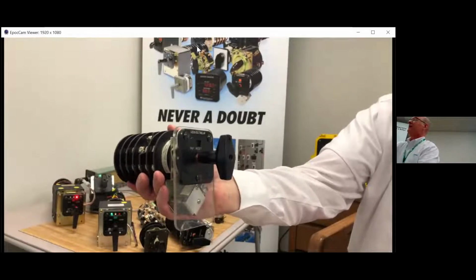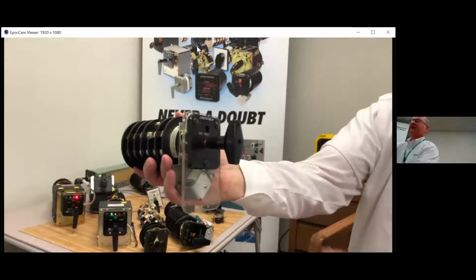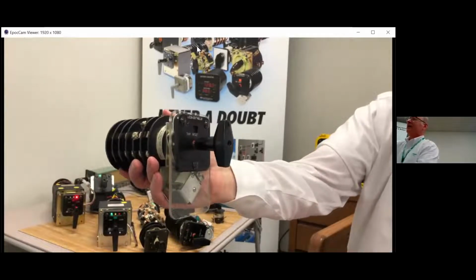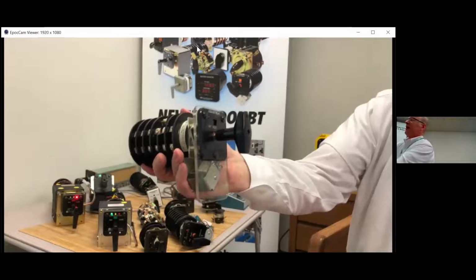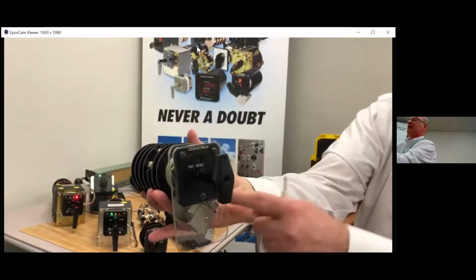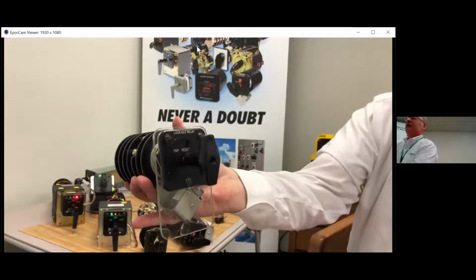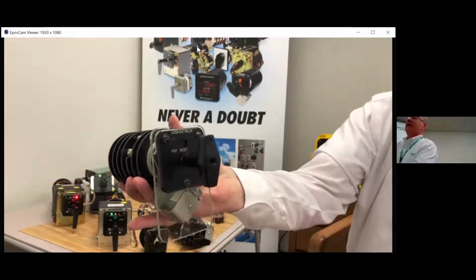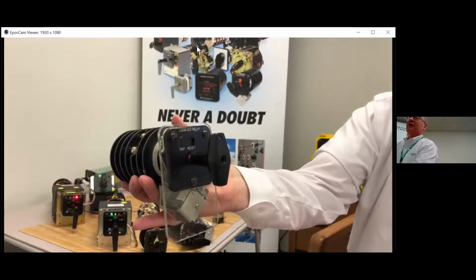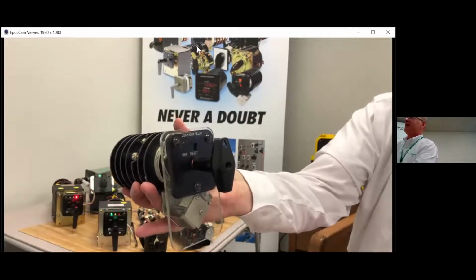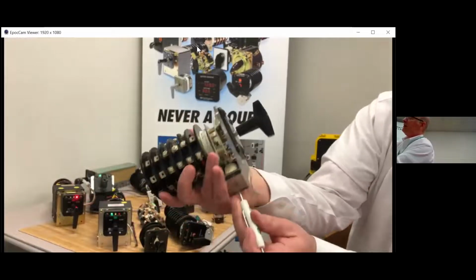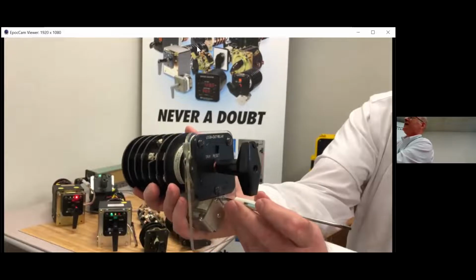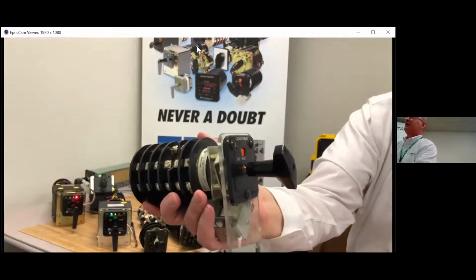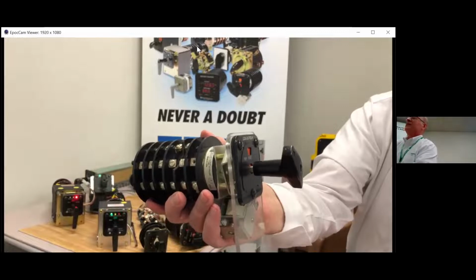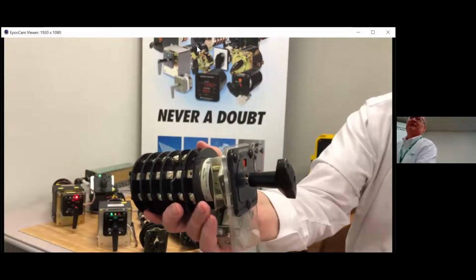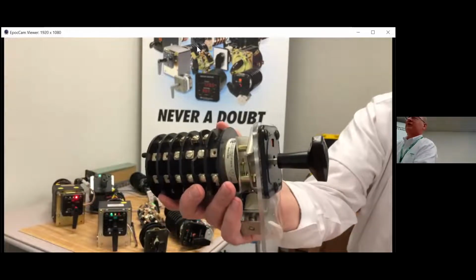The only thing that I can do is wait for a protective relay that's out in the field to trip this device. And to do that, there's a solenoid here that is basically mechanically holding a spring mechanism that is energized momentarily by a system protection contact. And when that system protection contact operates, it then trips the lockout relay. So once I do that, the mechanics is the speed. That mechanical spring is an 8 millisecond operation spring.